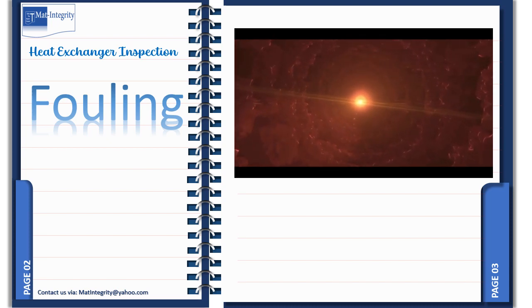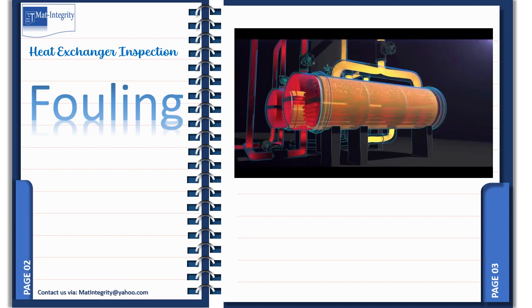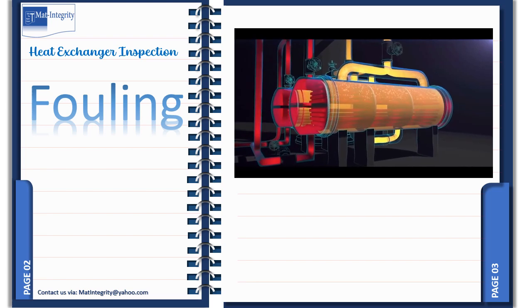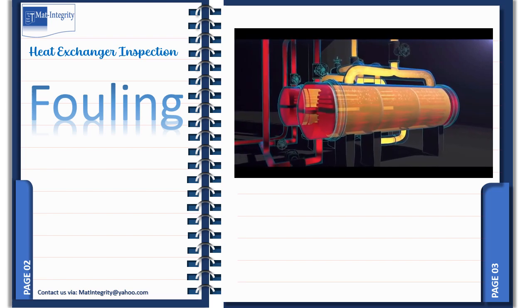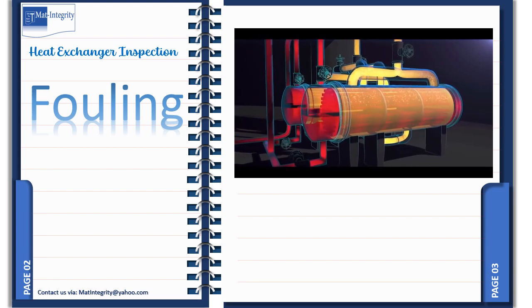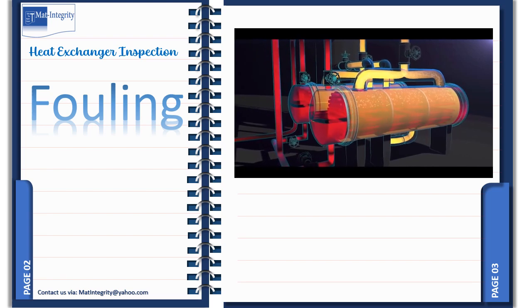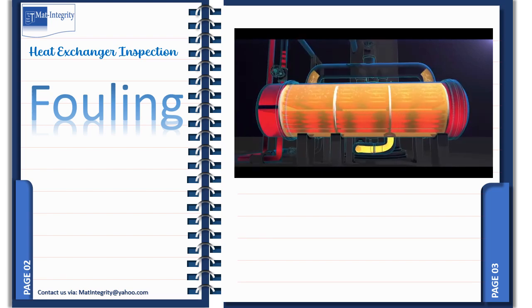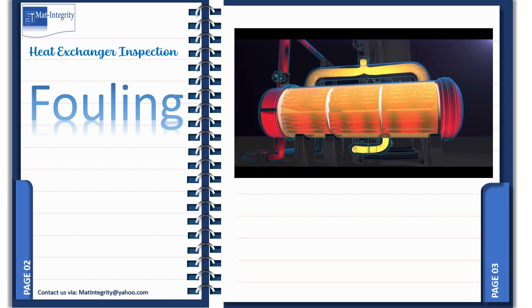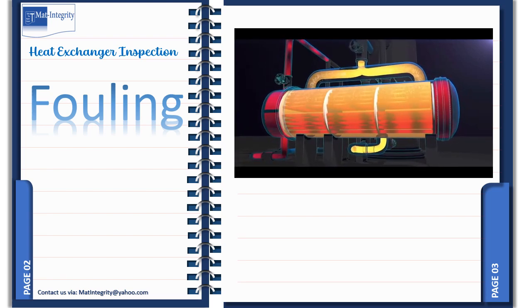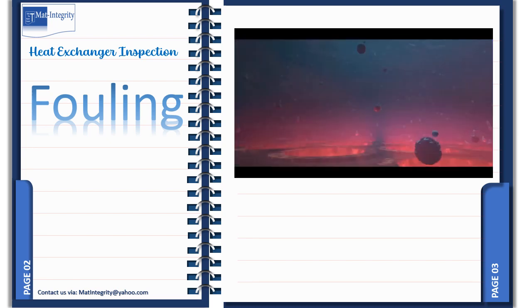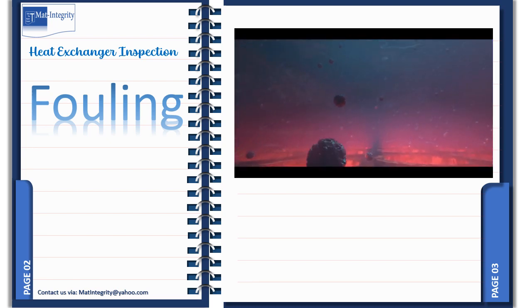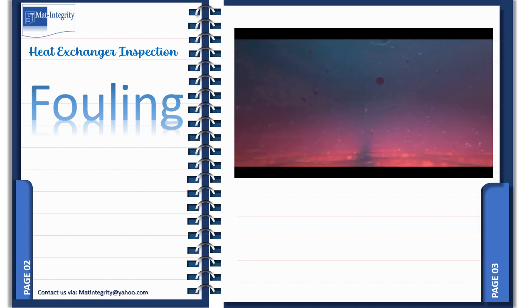Fouling affects the energy consumption of industrial processes and it can also decide the amount of extra material required to provide extra heat transfer surface employed in heat exchangers to compensate for the effects of fouling. In addition, where the heat flux is high, as in steam generators, fouling can lead to local hot spots and ultimately it may result in mechanical failure of the heat transfer surface.